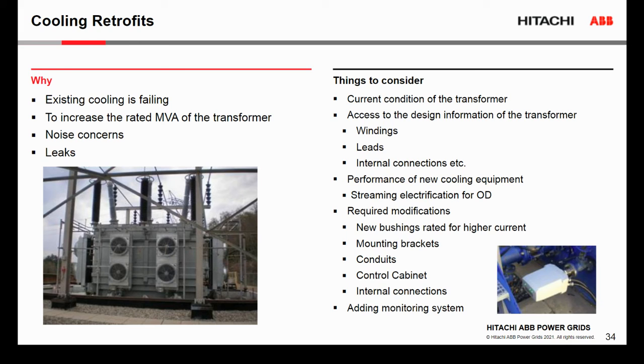First, we have to understand the current condition of the transformer. We have to understand how this transformer was loaded in the past, what is the actual aging of the transformer, what is the moisture content, and what is the current condition of the bushings and other components. Then, and it is important, especially when we want to increase the rated MVA of the transformer, we have to really know the design of the transformer. We have to know the design of the winding, leads, and internal connections, because by increasing the MVA, we increase the current density in the windings and the leads, and this will affect the aging of the transformer.